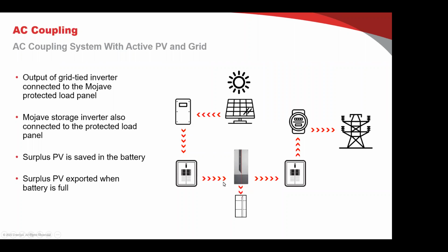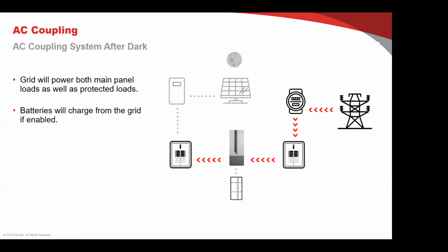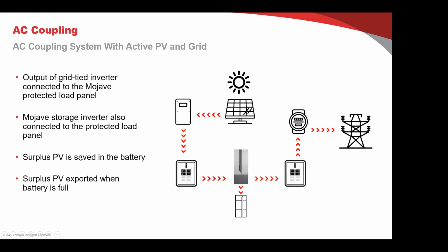Okay, so when the grid is running, our function is basically a copper wire. We're just passing through the energy from the array through the grid inverter for some self-consumption on that protected load panel, fill up the battery if it needs it, more self-consumption out here on the main load panel, and if there's anything left over, it goes on out to the grid. Then, at the end of the solar day, the sun goes down and the power comes back the other direction. So again, we're still in a pass-through mode, acting like a piece of copper wire, passing energy through to the protected load panel. Then the next day the cycle starts over again.